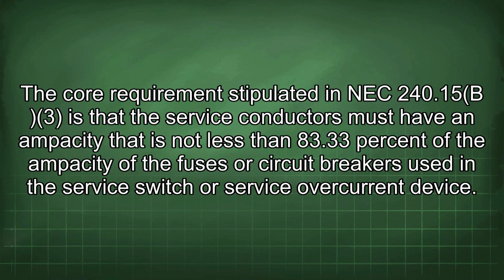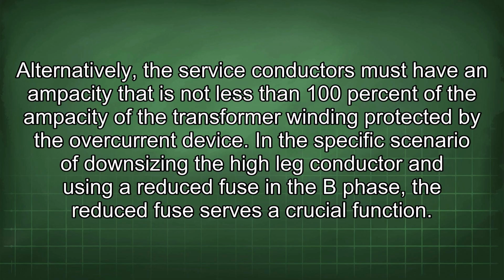The core requirement stipulated in NEC 240.15(B)(3) is that the service conductors must have an ampacity that is not less than 83.33% of the ampacity of the fuses or circuit breakers used in the service switch or service overcurrent device. Alternatively, the service conductors must have an ampacity that is not less than 100% of the ampacity of the transformer winding protected by the overcurrent device.